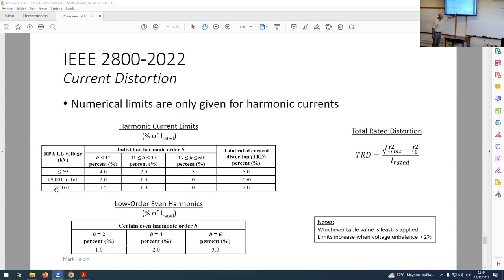We're making the same compromises with regard to the effect of even order harmonics that we talked about before. We're also, because we recognize that generation tends to be inverter-based, PWM, higher frequency, okay? We're using the same concept of total rated distortion, trying to capture the higher frequency type effects.